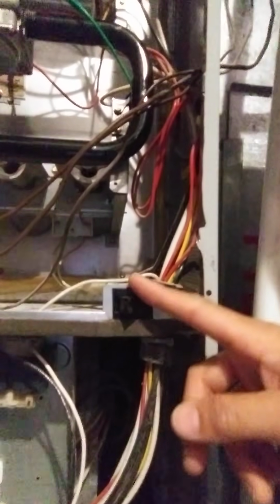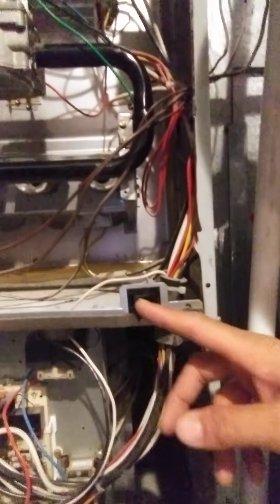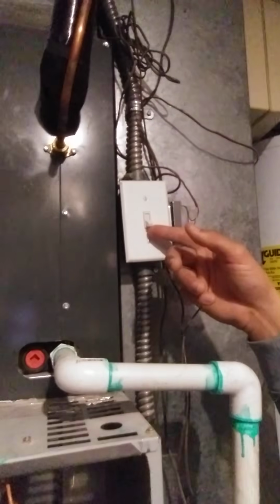And then what you would do is put the covers back on, because if you can see it right here, there's a switch that will cut power off to the unit if that is not depressed. So you want to put your bottom cover back on to make sure that's depressed, and flip your switch back on again, and then go ahead and turn your heater on to a higher degree than what your house is currently set at right now. That way it'll tell the heater basically it needs to kick on, and then you will see if things function properly from there. In my case, this was not the particular problem, but it's the same method.